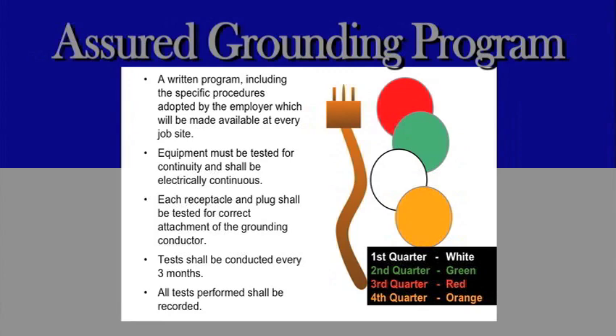Equipment must be tested for continuity and shall be electrically continuous. Each receptacle and plug shall be tested for correct attachment of the ground conductor. Tests shall be conducted every 3 months. All tests performed shall be recorded. First quarter white, second quarter green, third quarter red, fourth quarter orange.